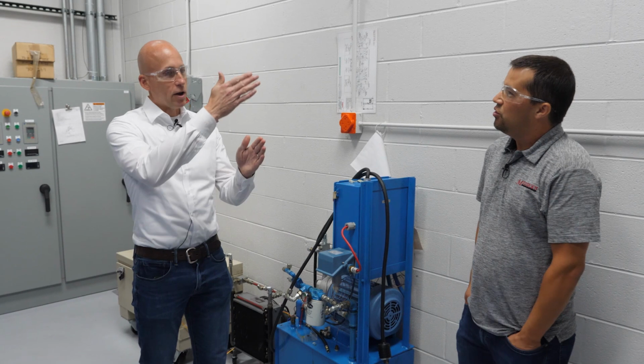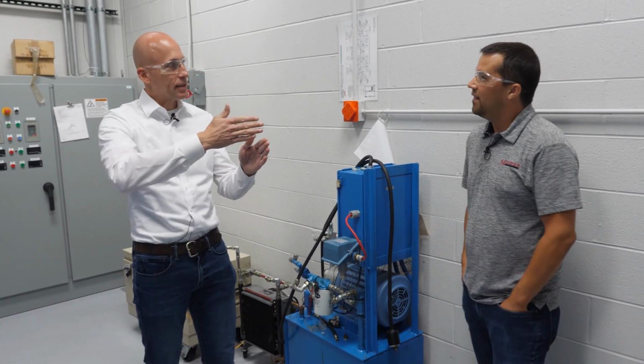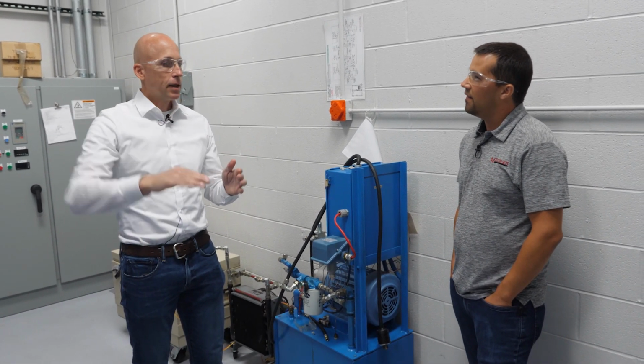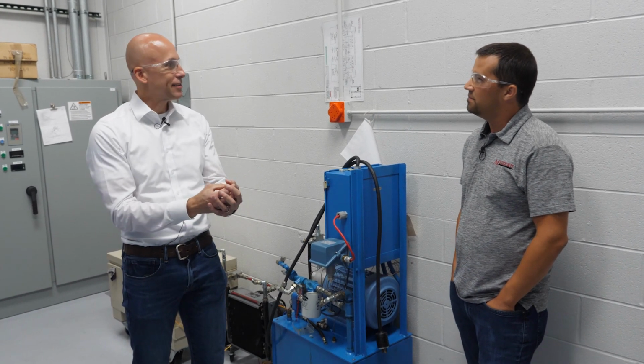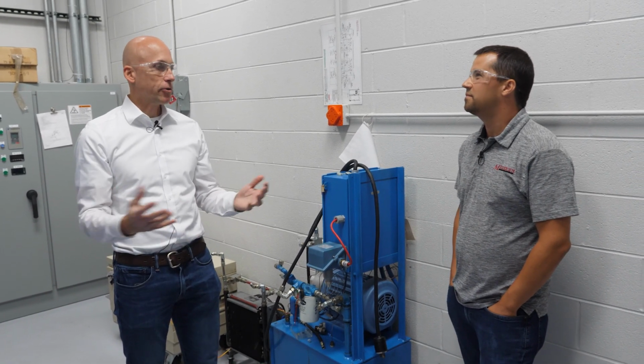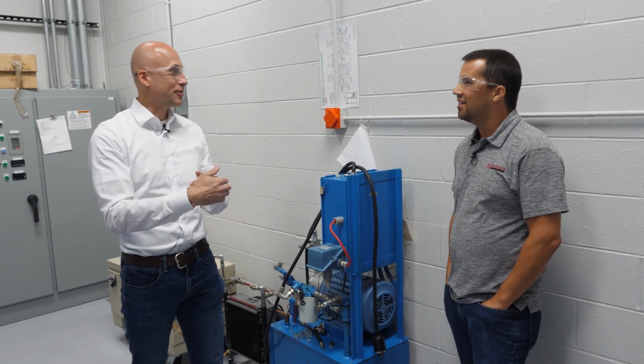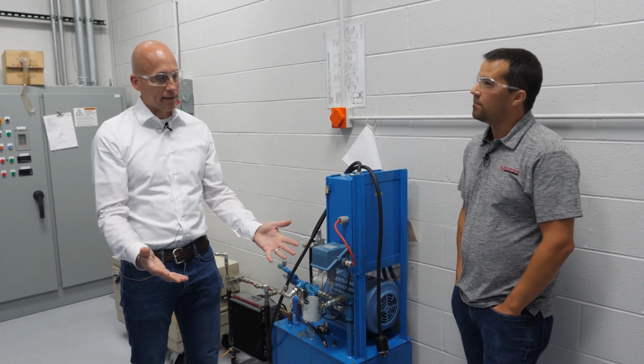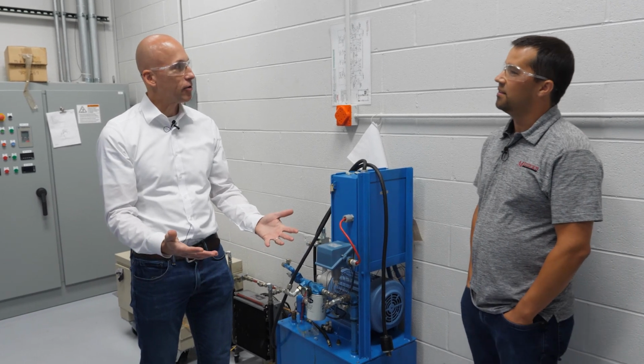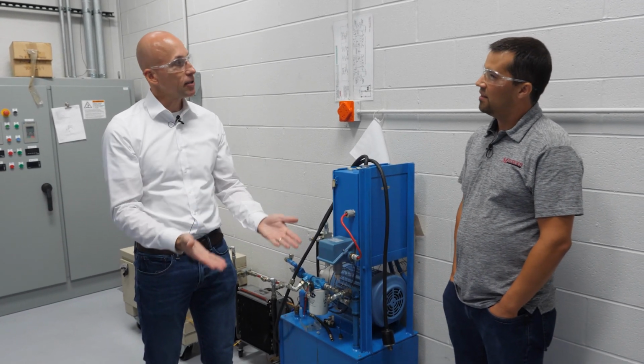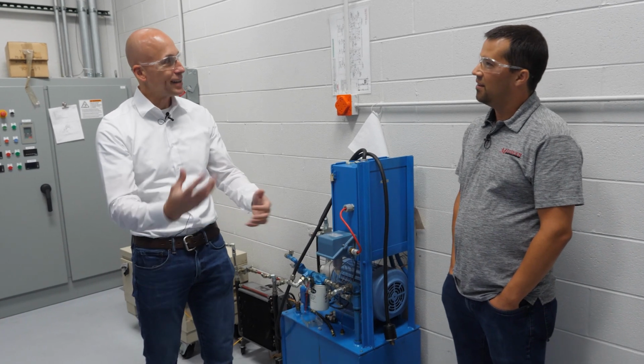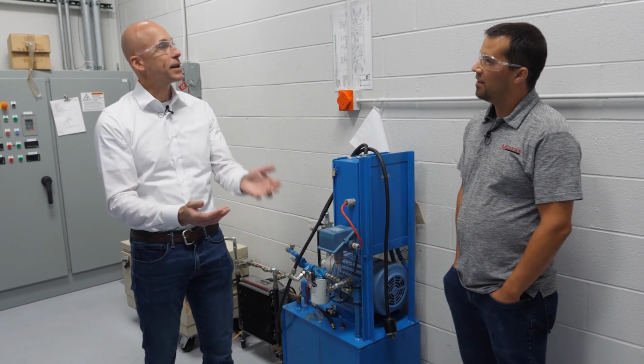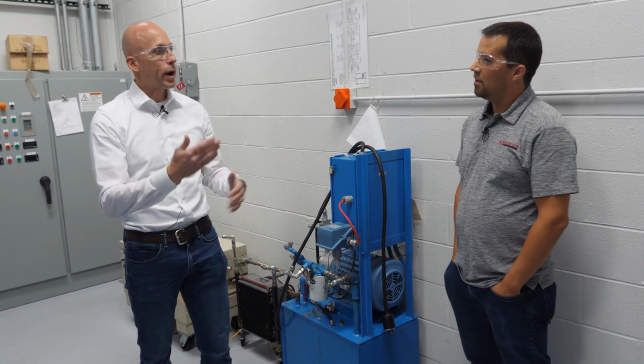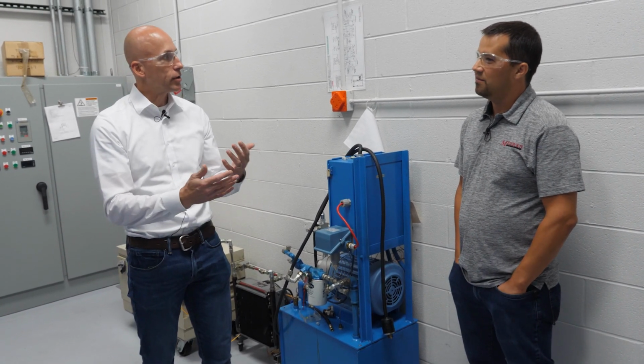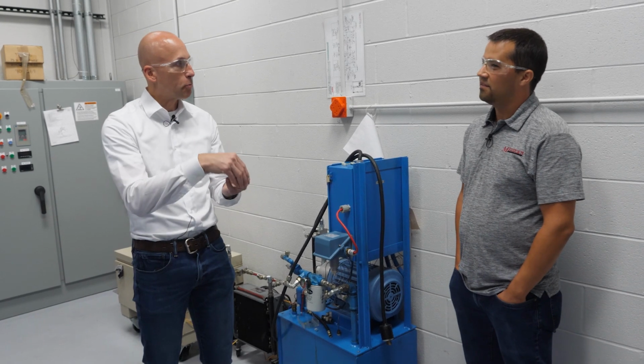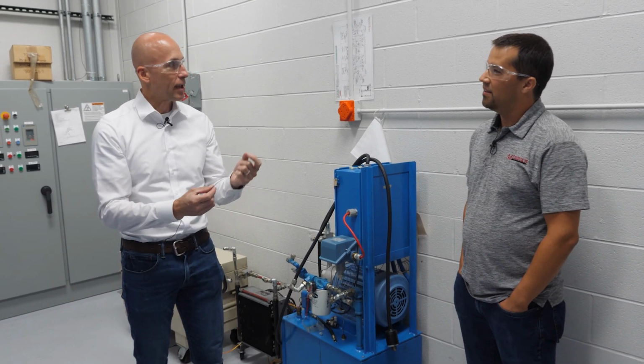Because we call it the wash tub effect. So it's at the beginning of the life and it's at the end. And at the end, the filters can only collect so much debris. Depending upon the filter and where it's located, if it has a bypass, that's the worst thing. The other thing is the tanks. The tanks collect contamination over time. And depending upon the level of the oil in the machine, that slurry, that oil can become more contaminated, and you're sending it through and it's just wearing down the parts. Eventually it could cause a seizure where the spool doesn't move anymore. That piece of contaminant caused a problem.